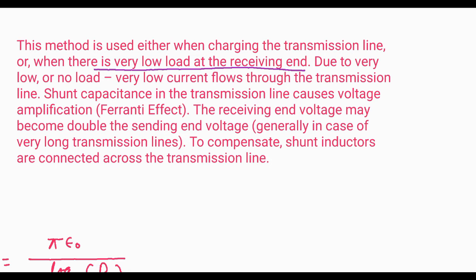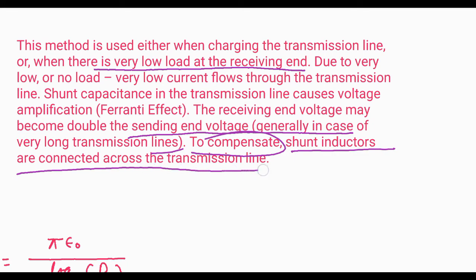So to regulate that shunt capacitance, or to nullify the Ferranti effect, we use shunt inductance. The receiving end voltage may become double the sending end voltage. This is the definition actually. To compensate this, shunt inductors are connected across the transmission line.